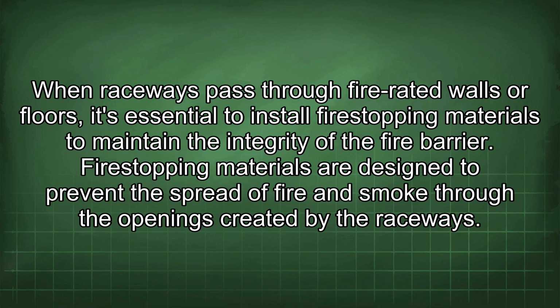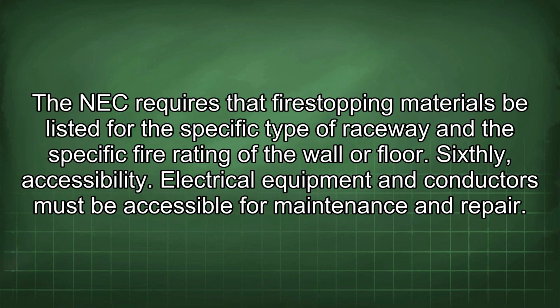Fifthly, fire stopping. When raceways pass through fire-rated walls or floors, it's essential to install fire-stopping materials to maintain the integrity of the fire barrier. Fire-stopping materials are designed to prevent the spread of fire and smoke through the openings created by the raceways. The NEC requires that fire-stopping materials be listed for the specific type of raceway and the specific fire rating of the wall or floor.